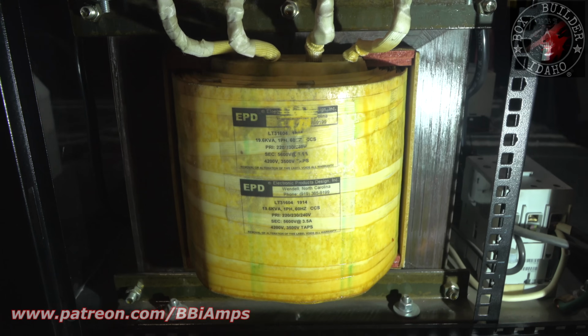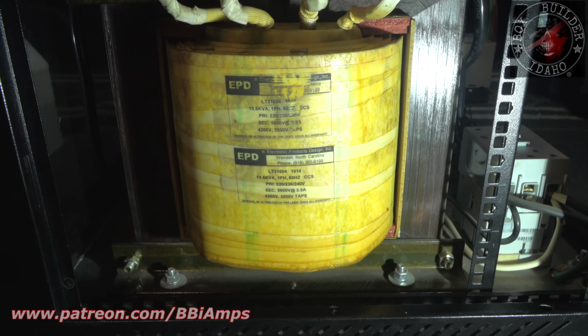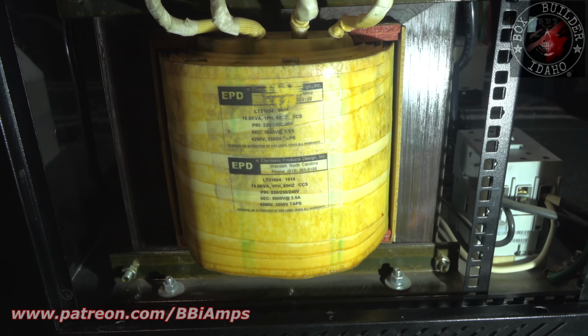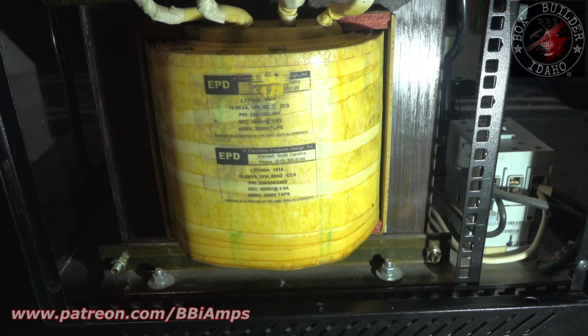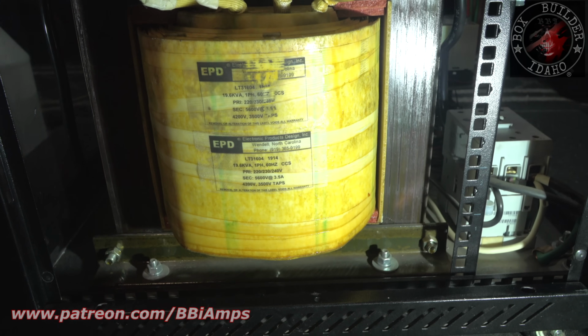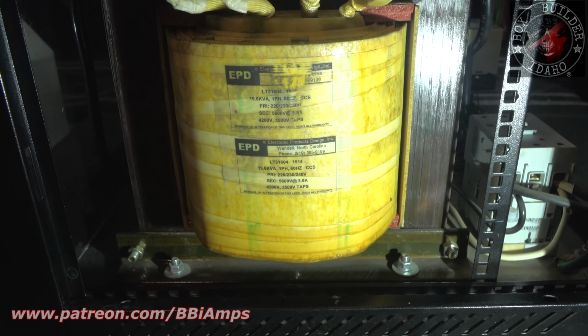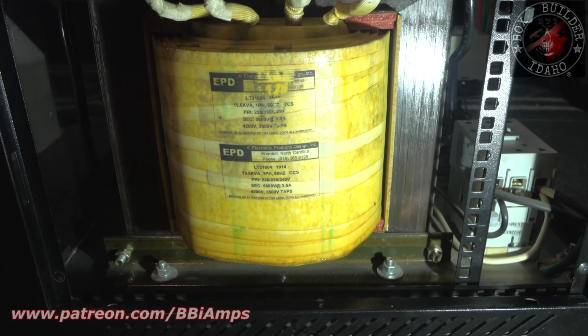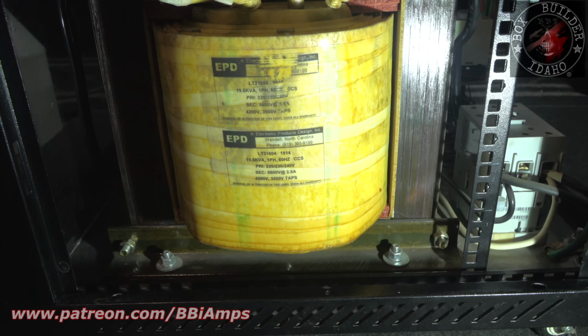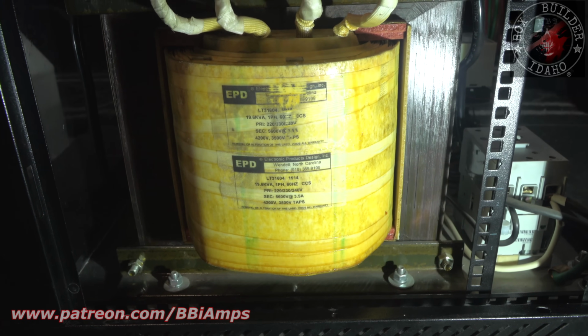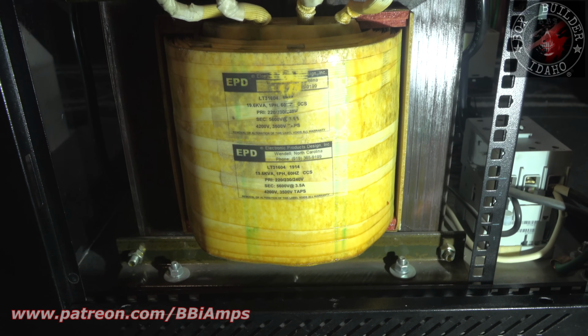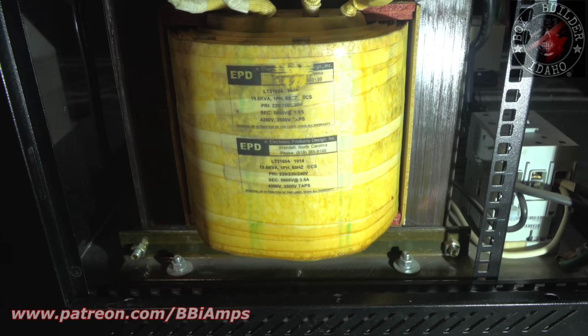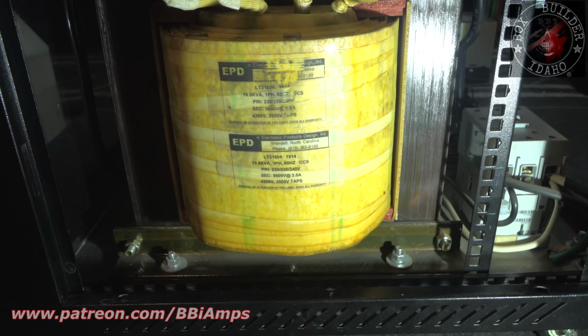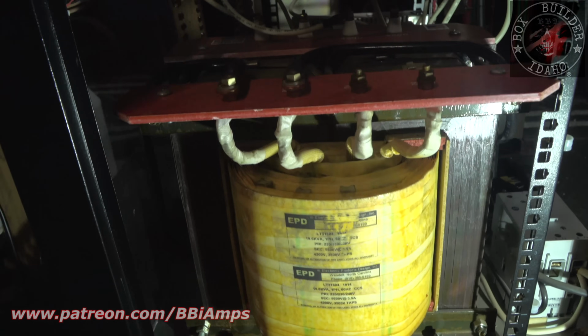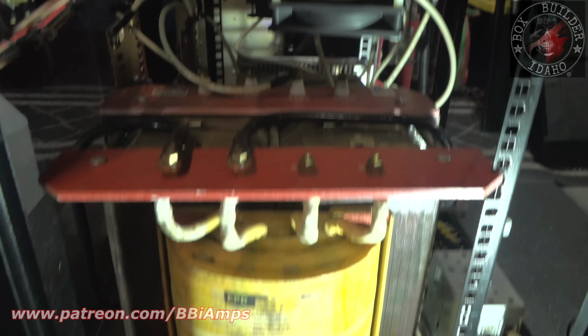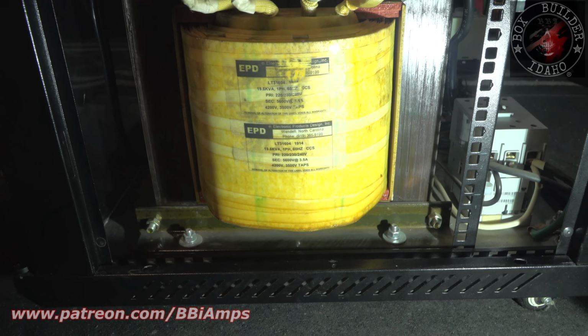That's the beauty of this transformer, is that you can make it run 2 threes, or probably 4 threes. And remember, when you go down in voltage, you pick up amperage. The top tap, you can run everything in between. This transformer will run a 5,000, it'll run a 10,000, 2 sixes, no problem, with headroom. The 10,000, you can run it full out. So by changing the taps, the primary and secondary taps, you can achieve all kinds of different voltages.